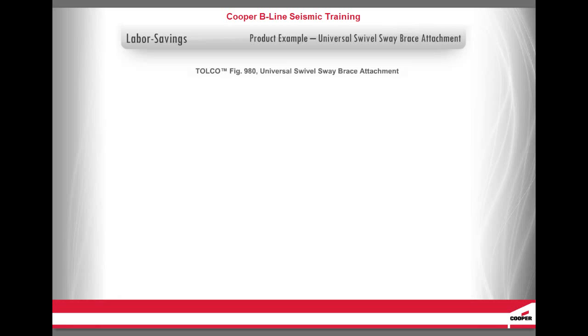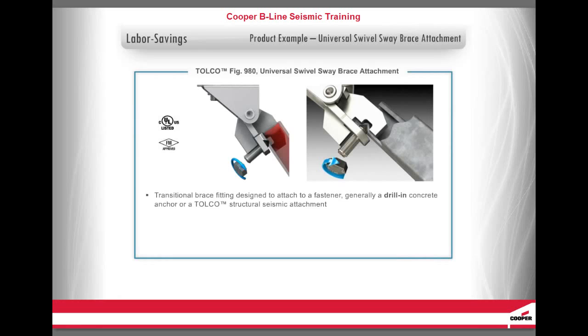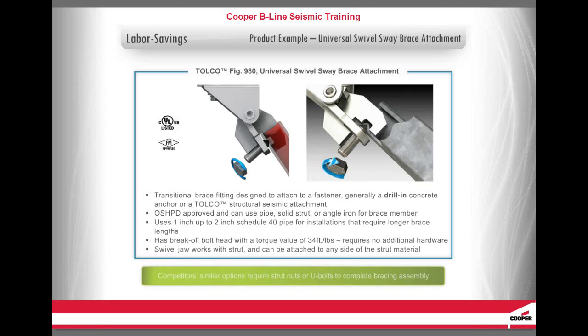Another advantage of rigid bracing is the ease of installation. The Figure 980 Universal Swivel Sway Brace Attachment is a transitional brace fitting designed to attach to a fastener, generally a drill-in concrete anchor or a TOLCO structural seismic attachment. It is OSHPD approved and can use pipe, solid strut, or angle iron for a brace member. It uses one inch up to two inch Schedule 40 pipe for installations requiring longer brace lengths. It has a break-off bolt head with a torque value of 34 foot-pounds and requires no additional hardware — you can simply take it out of the box and install. Its swivel jaw works with strut and can be attached to any side of the strut material. In contrast, competitors' similar options require strut nuts or U-bolts to complete the bracing assembly, requiring more material and time to install.